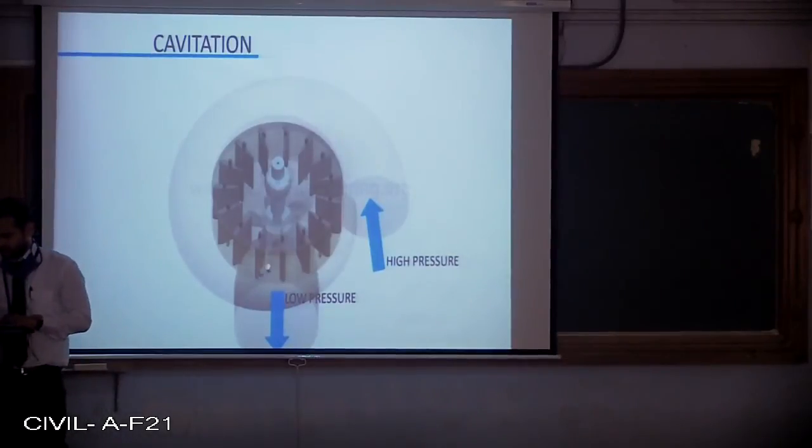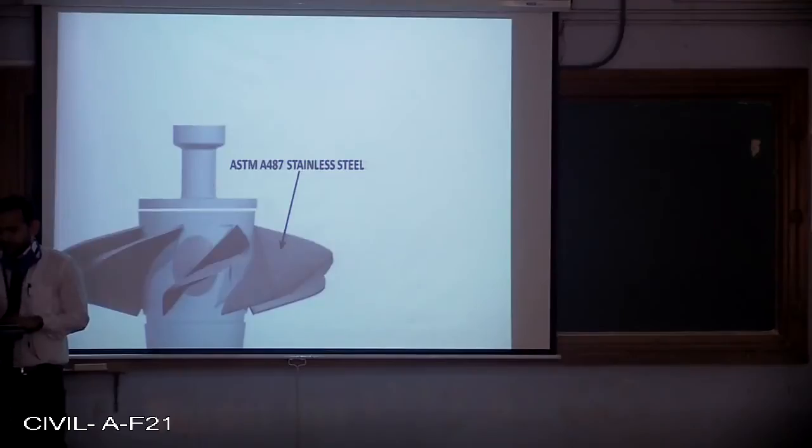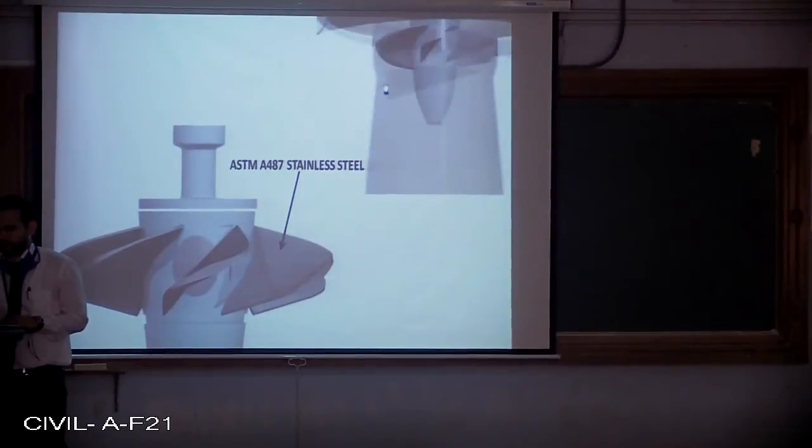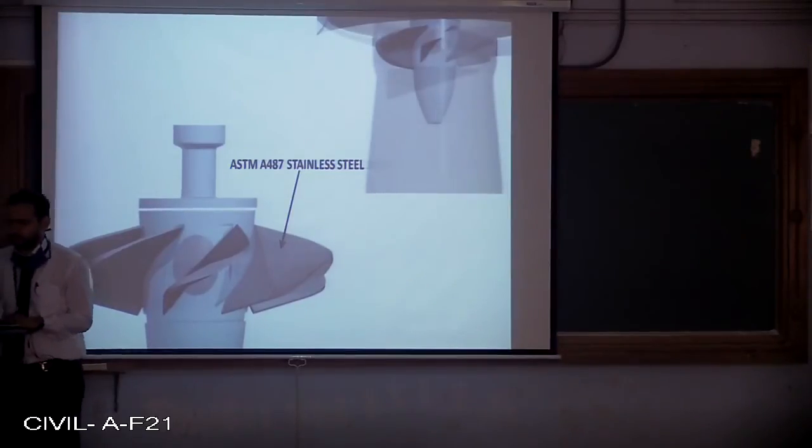Since in most of the regions pressure goes very low, damage due to cavitation can be reduced by using suitable blade material and use of anti-cavitation fin. The draft tube, which transforms dynamic pressure to static pressure due to its increasing area, also helps in reducing cavitation effect.